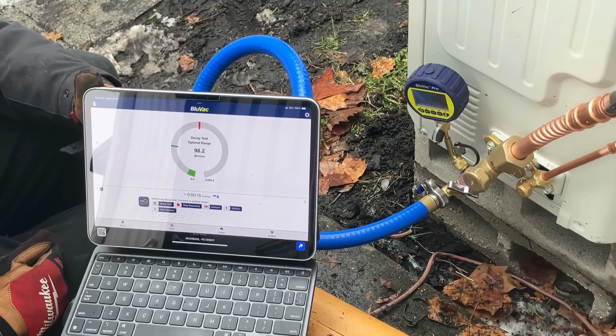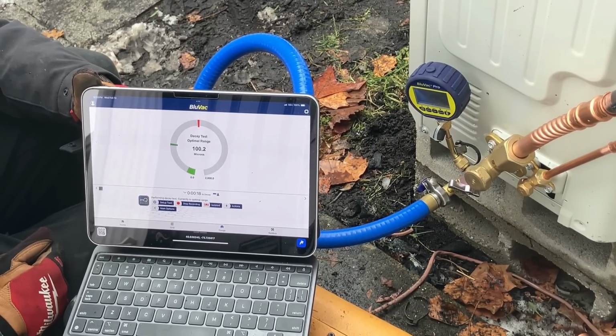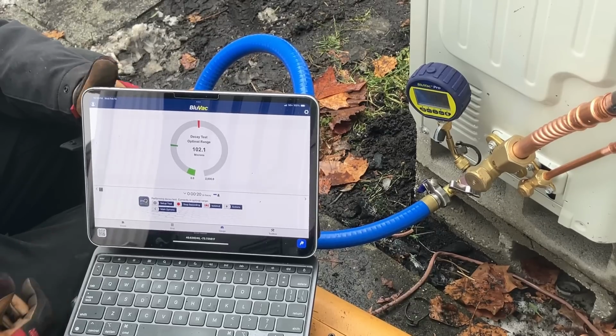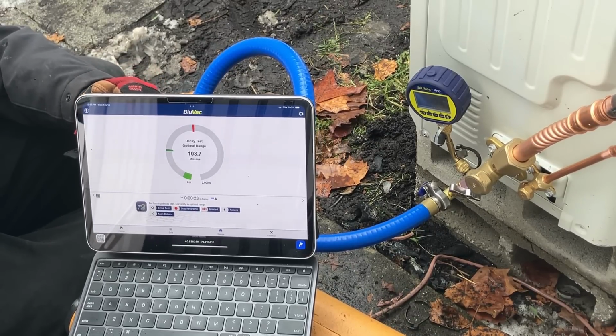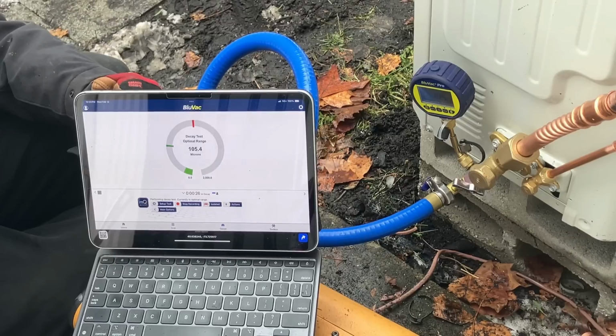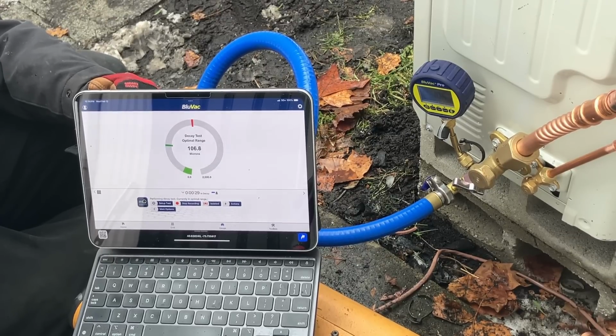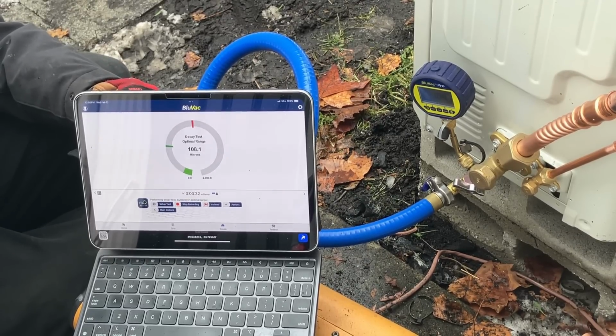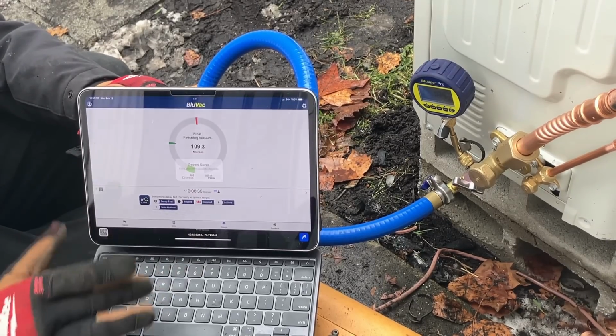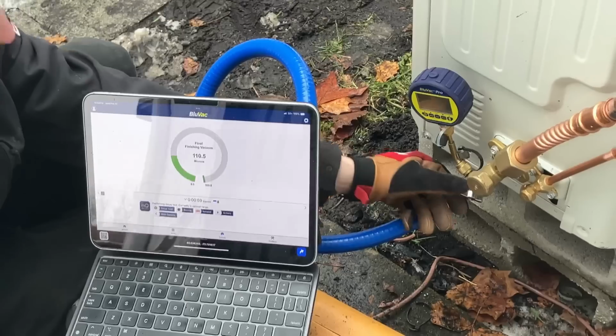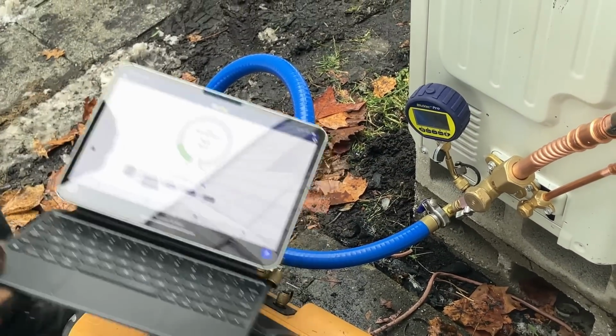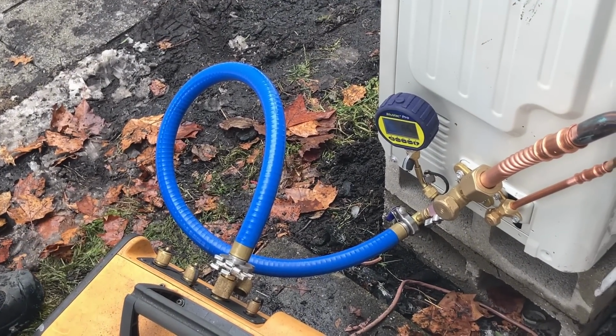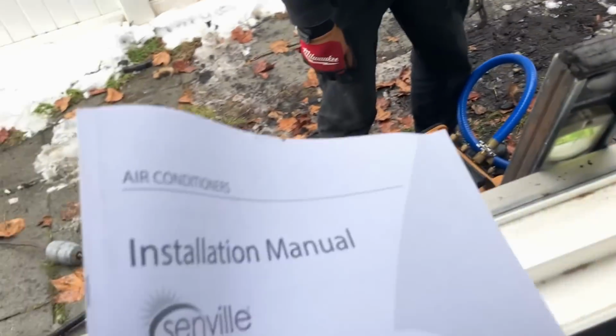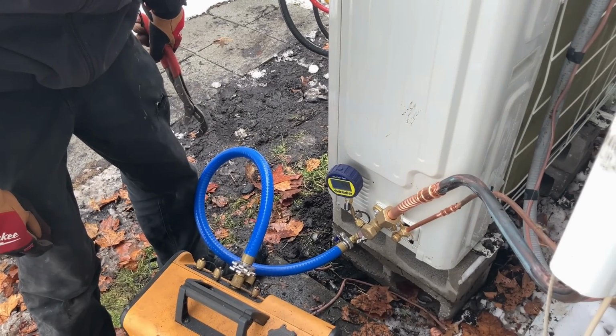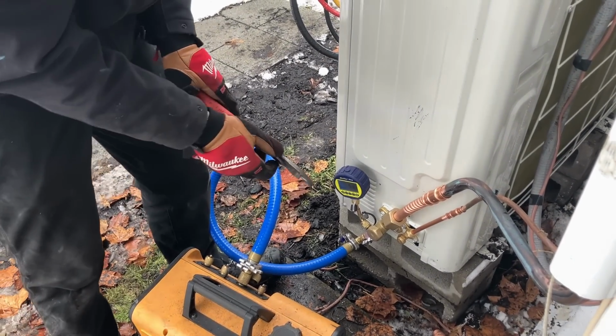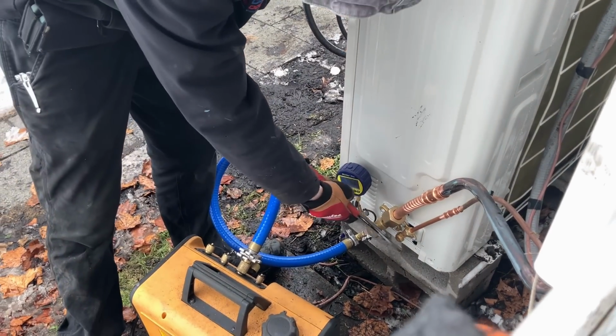96 microns, 97, 98. 100 microns, 101. There you go, the decay has passed at 109 microns. Industry average, industry standard, 500. We go above and beyond. Just a heads up, Daniel, in the installation manual, they say open both ports gently. They don't specify which one to open or close first. So just remember, just open gently.